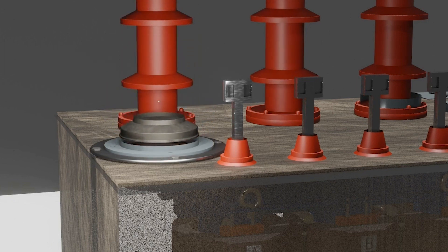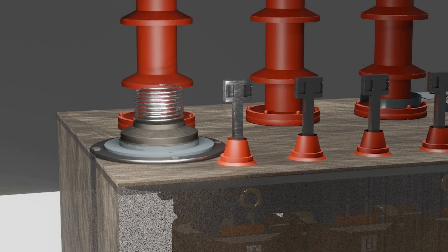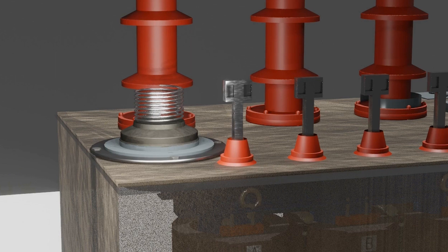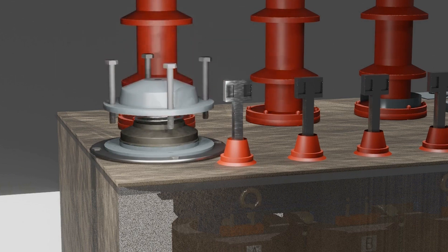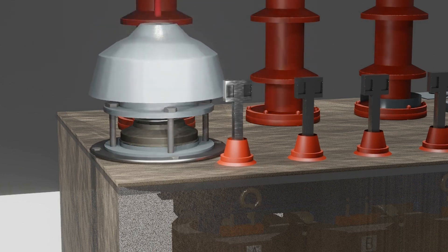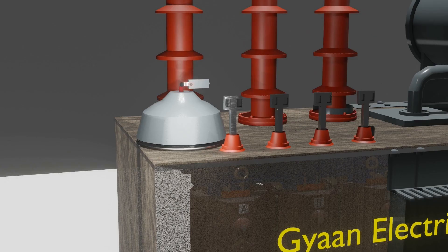So in normal condition disc is always in close condition due to this spring tension. So this spring always provide pressure on disc. So disc kept connected with the flange as you see here. After that, top mounting plate is installed. Then finally flag and limit switch is installed. So this is how PRV is constructed.